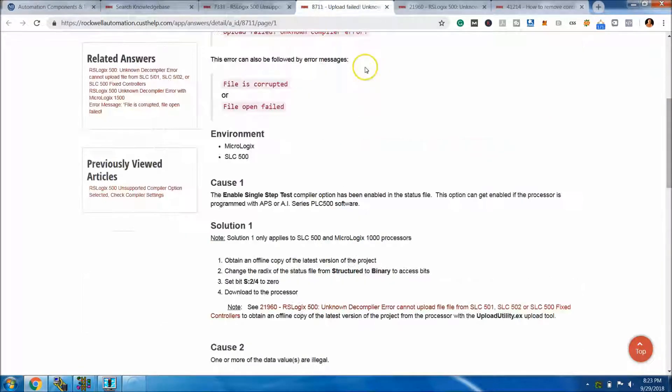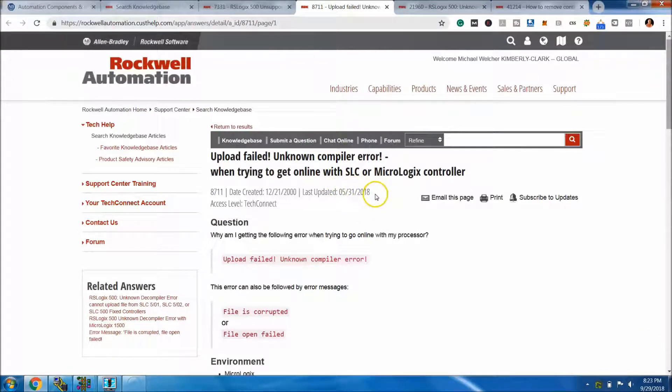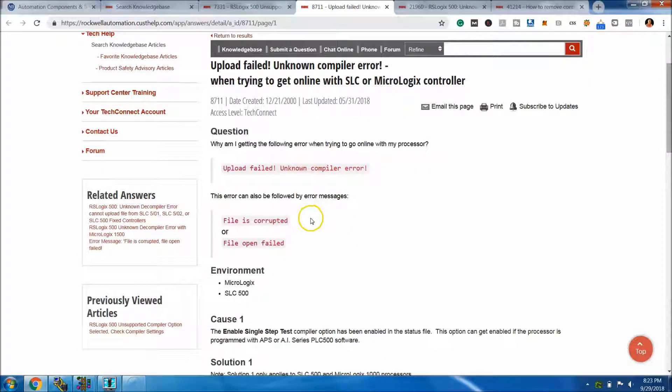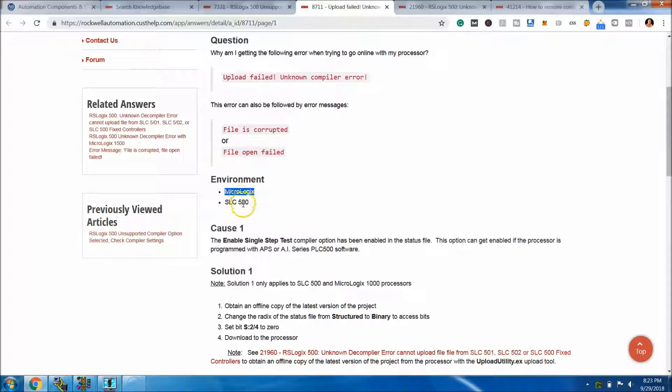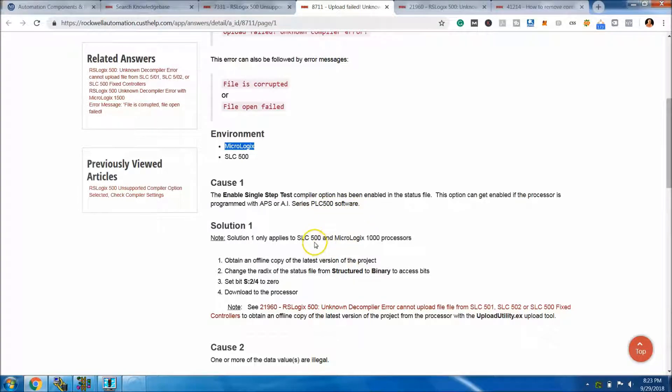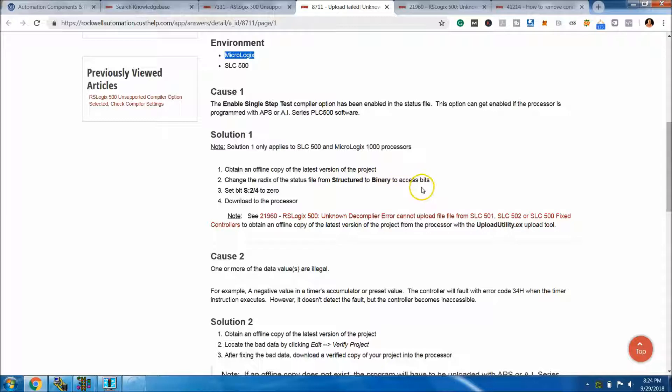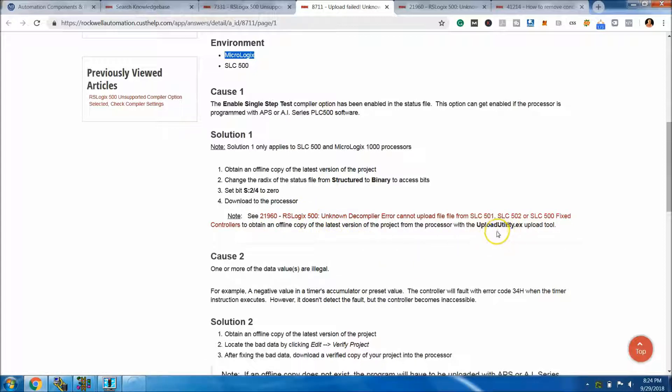If you look at another tech note, they both reference the same thing. This tech note was updated 5/31 of 2018. It has an unknown compiler error. The environment is still a Micrologix, not ControlLogix. It's still saying the same thing: the enable single step compiler option is enabled. The solution again is to obtain an offline copy of the latest project, change the radix from structure to binary to access the bits, set the S:2/4 bit to zero, and then download the project.